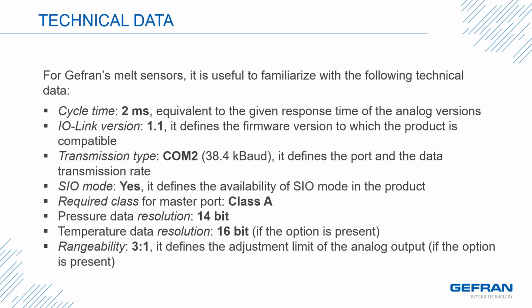Now I'd like to provide some additional supporting material and some unique information regarding IO-Link. There are a few important pieces of information regarding Gefran's implementation of IO-Link in our melt pressure sensors. The first I'd like to point out is the cycle time, or the equivalent to the response time in an analog transmitter, is 2 milliseconds. That means that the implementation of the digital I/O circuitry to support IO-Link has not affected the response time of our standard sensors. We comply or operate to IO-Link version 1.1. This is the firmware version. This is the current firmware version established for IO-Link.